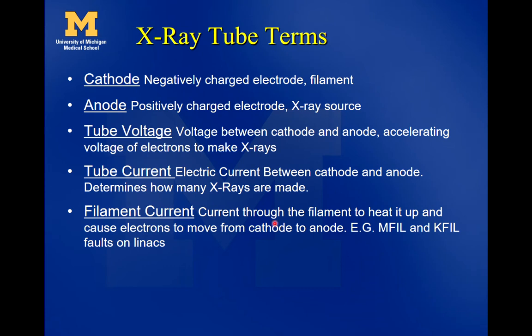The tube current is the electrical current between the cathode and the anode. It determines how many x-rays are made — more tube current means more x-rays produced, and also more heat on the anode. These days, it's usually done by pulsing. The filament current is the current through the filament to heat it up and cause the electrons to move from the cathode to the anode after the voltage is applied. They won't move just on their own.